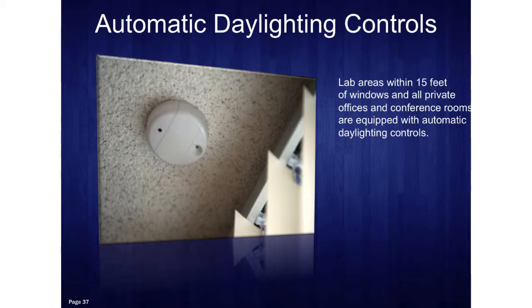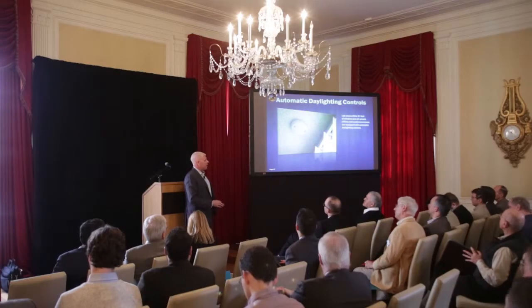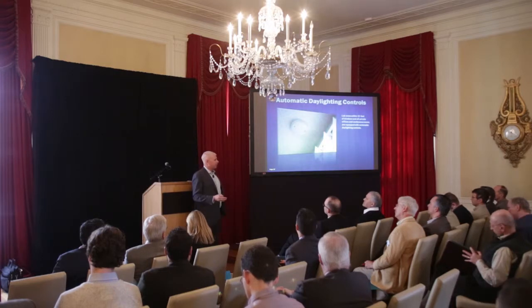Automatic daylighting controls have taken leaps forward in just the last 5 years. When we built Gross Hall, one key aspect was that everything within 15 feet of the window line - private offices, conference rooms, laboratories - would have automatic daylighting controls. What's gotten better is the calibration, the auto-calibration and recalibration of these systems.